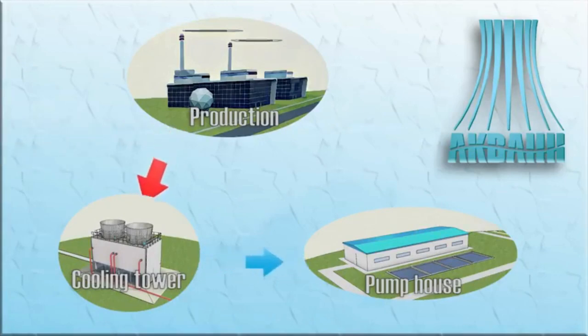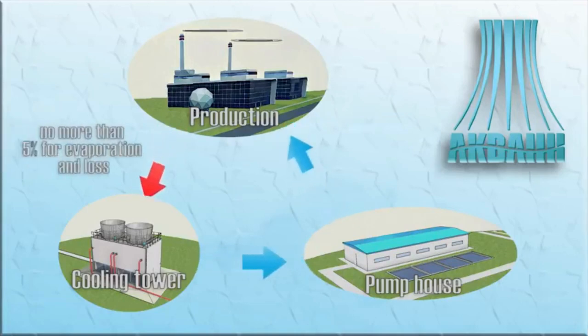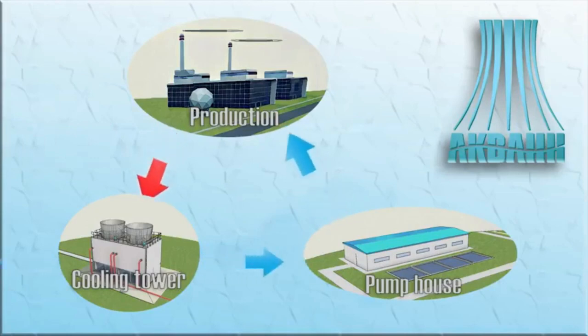After cooling, the main volume of recycled water is fed back into the process cycle. Usually no more than 5 percent of water is lost to evaporation, drip loss, leakage, and discharge into a blow-down system. Losses are replenished by fresh water makeup.